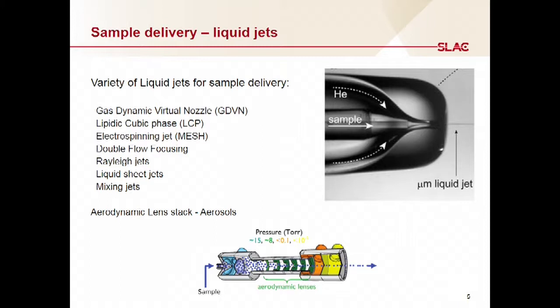And then using this high pressure helium sheath flow focusing, you can focus down to this 1 micron jet. It goes at very, very high speeds, around 10 meters per second. And so you can easily match the 120 hertz rep rate that you need. For other samples, which perhaps do not like the liquid that is here, or if you have a protein crystal that does not like water or whatever buffer that is there, there's a lipidic cubic phase jet, which is typically a slow-moving jet that is typically very viscous, and if your sample is more amenable to that kind of material or that kind of solution, you can use that.